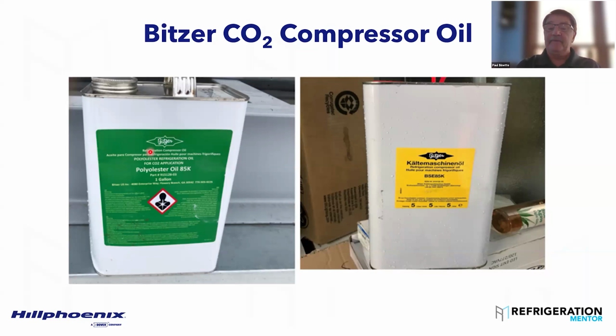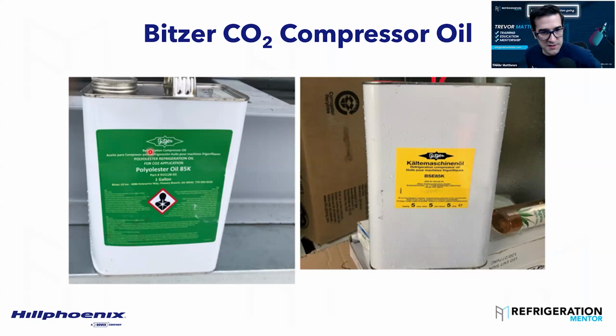you get the correct oil. We've been shipping Bitzers forever, and we did ship a Copeland rack with Bitzer oil, and the contractor caught it two weeks in advance and called me up. I got the right oil delivered. Make sure you have the right oil on site. Bitzer uses a BSE 85K, and depending on whether it's subcritical, they'll use a different oil. And Copeland's an RL68, I think it's RL68. Is that right? That's correct.